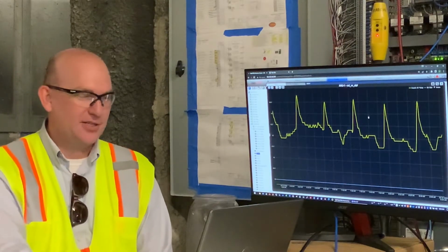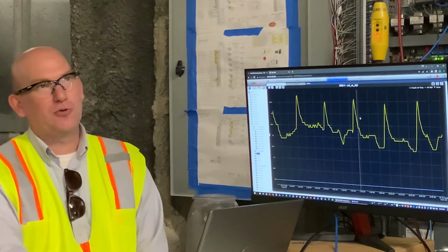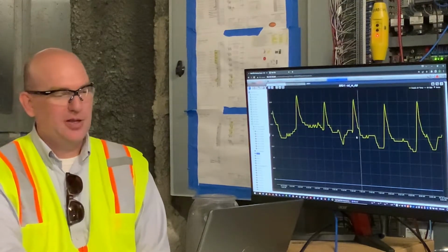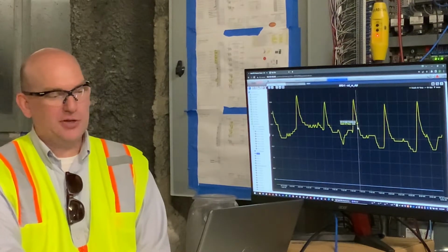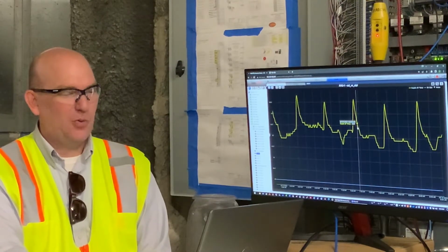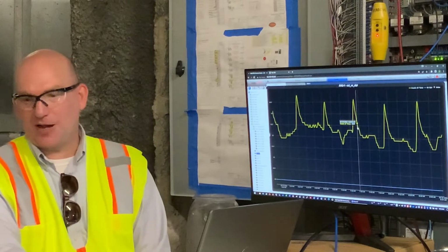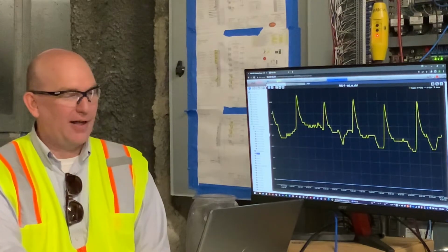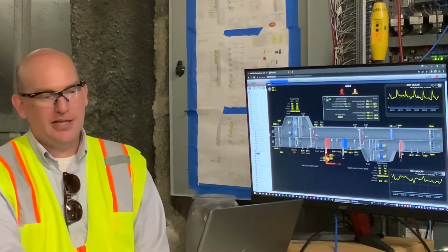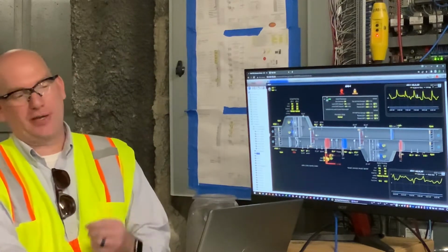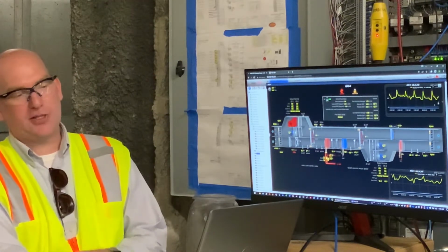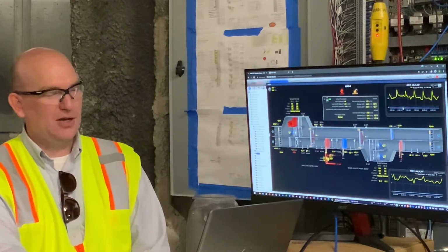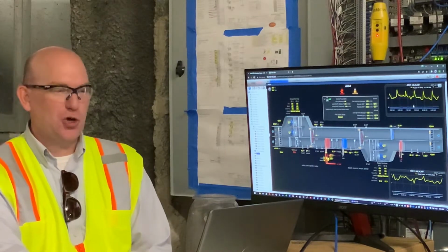The custom trends. When I started working for Radius, the trending has always been a part of the automated logic system, but what I realized very quickly was that if you ever have problems, the way that you always fix them, it always centers around the trends tab. Everything centers on that. And so that was something that I like to drive in all the graphics, is building not just a single trend, like showing just what the supply air temperature was, but a trend that has multiple points inside of it that help to do troubleshooting and help to show you what's actually happening in the unit.